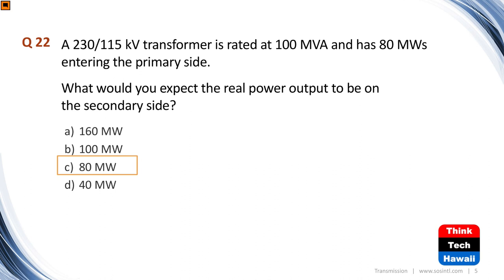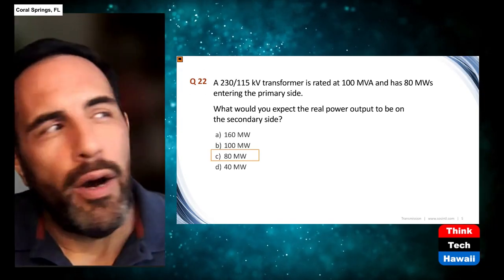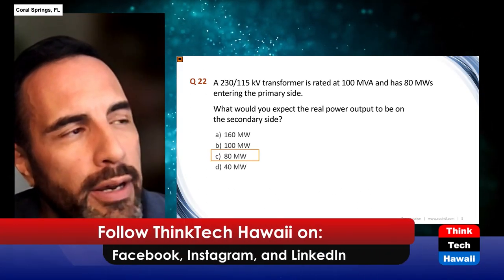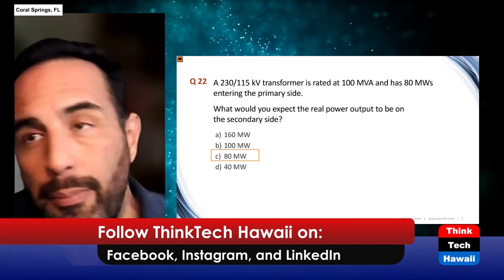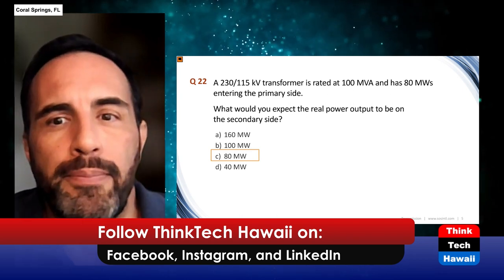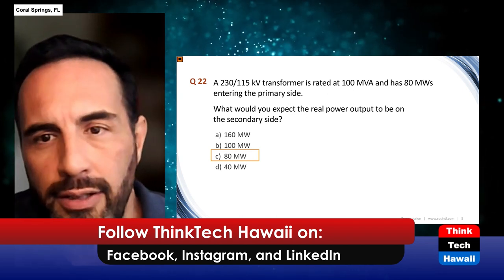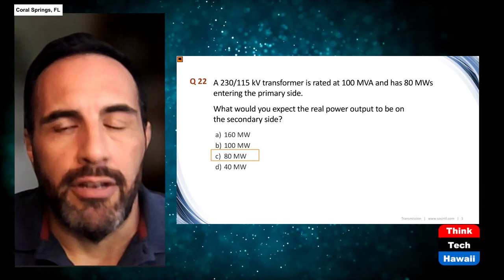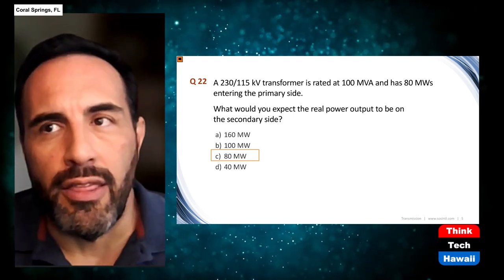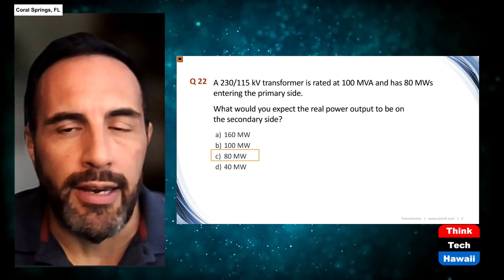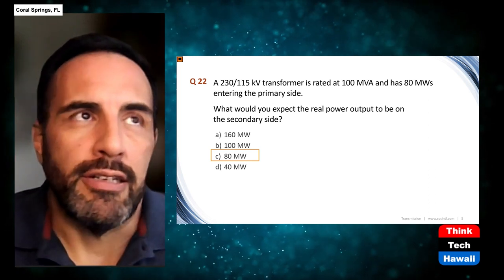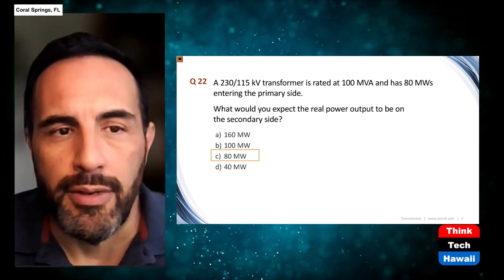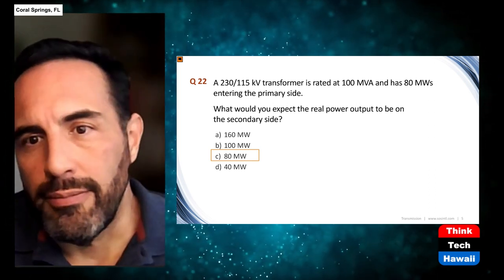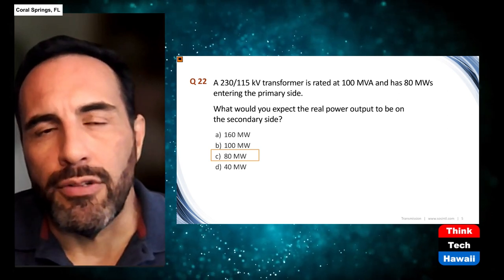So that's another important thing to remember. Why is voltage oftentimes stepped up from a plant, for example? Well, ideally, the higher the voltage, if you're carrying the same amount of megawatts, the thinner the line can be. So you don't have to have such a thick conductor, especially out there in a high voltage transmission system. That's another advantage of stepping up voltages.